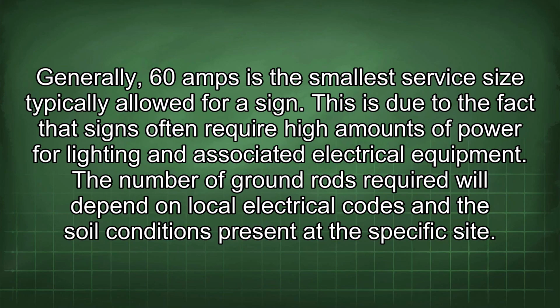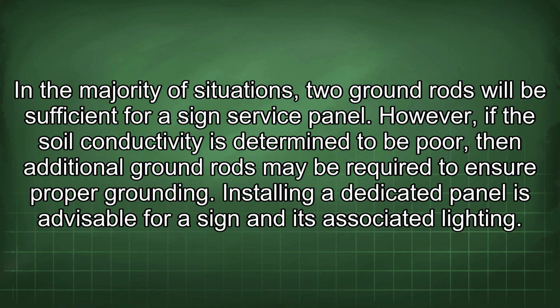Generally, 60 amps is the smallest service size typically allowed for a sign. This is due to the fact that signs often require high amounts of power for lighting and associated electrical equipment. The number of ground rods required will depend on local electrical codes and the soil conditions present at the specific site. In the majority of situations, 2 ground rods will be sufficient for a sign service panel.